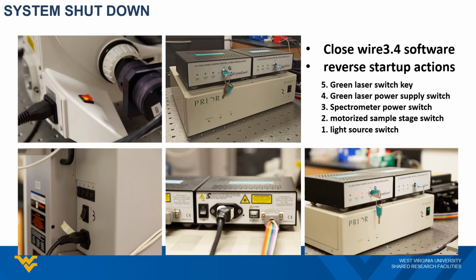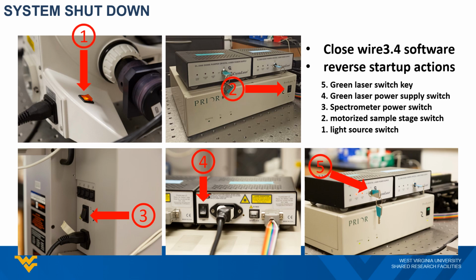To shut down the system, first, please close the Wire 3.4 software. We usually do this before shutting down the hardware, since if we leave the software on while shutting down the hardware, we will receive error messages for missing communication. Then we just simply follow the reversed order as the startup procedure. Turn off the laser key, shut down the laser power supply, turn off the spectrometer, turn off the motorized stage control box, and turn off the microscope light source.